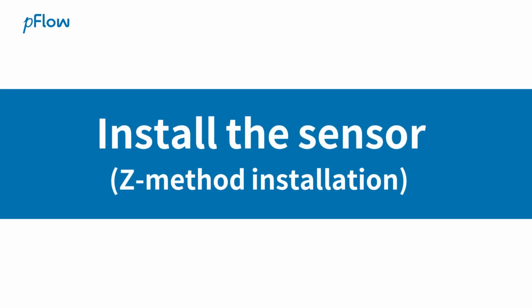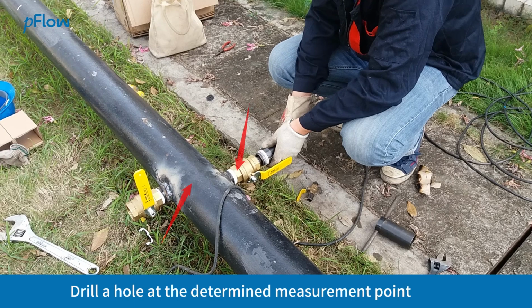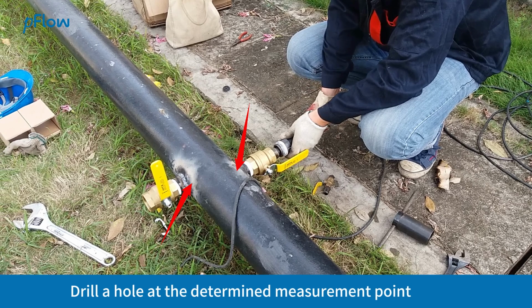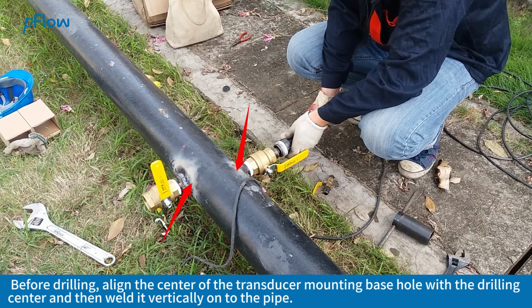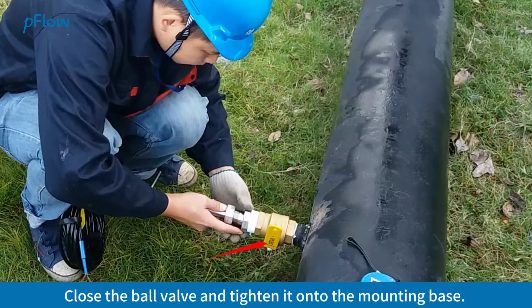Install the sensor. Z method installation. Drill a hole at the determined measurement point. Before drilling, align the center of the transducer mounting base hole with the drilling center and then weld it vertically onto the pipe. Close the ball valve and tighten it onto the mounting base.